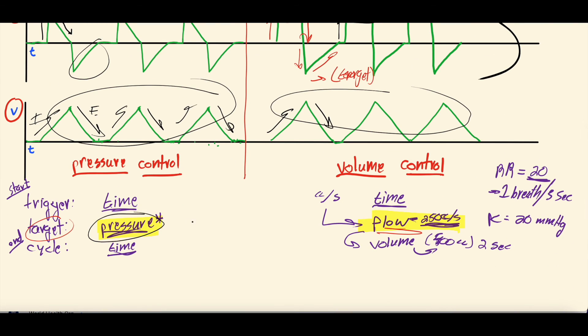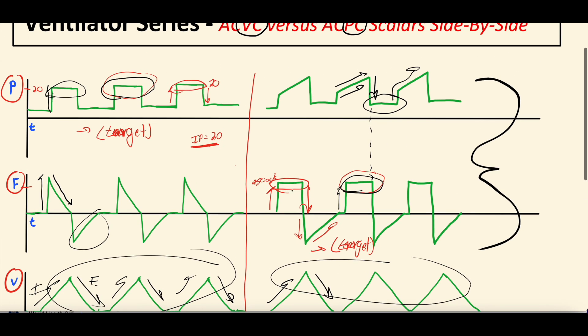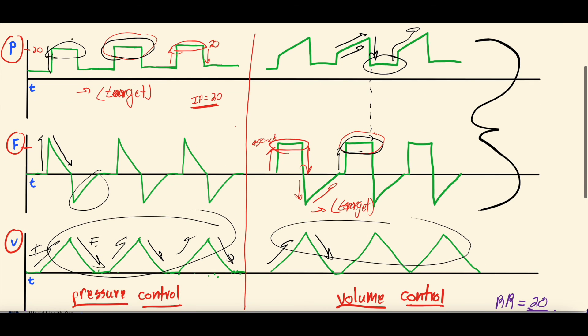So the big differences in scalars between modes are the pressure scalar and the flow scalar. Remember: in pressure control, the target is pressure, so you get the flat top on the pressure scalar. In volume control, the target is flow, so you get the flat top on the flow scalar. Hopefully that was helpful — this video just brings those two other videos together, so definitely check those out. Let us know your thoughts, comments, and questions below. As always, stay well, keep learning, subscribe, hit the bell button, and we'll see you next time. Bye.